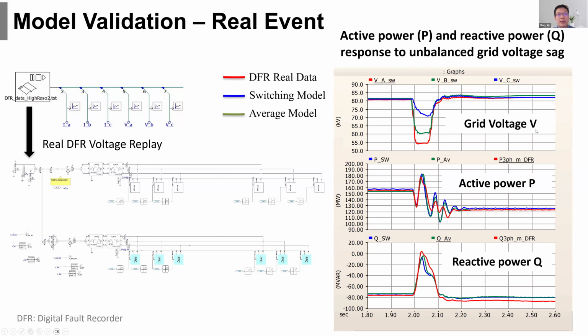The first figure shows the grid side voltage. This is the real grid side voltage from the real event. This is an unbalanced grid voltage sag at different phases. The red curve is phase A, the green curve is phase B, and the blue curve is phase C. We can see there is unbalanced voltage sag across three phases during this event. And then the second figure and the third figure are the active power response and reactive power response to this voltage sag event. In these two figures, the red curve is the real data from the DFR. The blue curve is the simulation results from our switching model, and the green curve is the simulation results from our average model. You can see that they have a very similar pattern and they align well with the real field data.